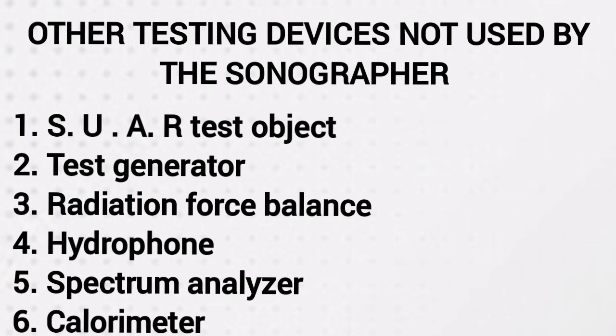Other testing equipment, which is typically not used by sonographers or sonologists, is the SUAR test object. SUAR stands for sensitivity, uniformity, and axial resolution. The other one is a test generator, or pulse burst generator, also called an electronic test object. The third is the radiation force balance. Then you have the fourth, hydrophone, fifth, spectrum analyzer, sixth, calorimeter.